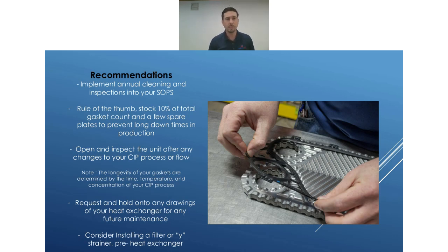A rule of thumb we go by is it's a great idea to have 10% of your gaskets in stock at your facility just in case. If something happens - pressure and you blow out a gasket, or you open the heat exchanger and tear a gasket - you have some readily available, and you're not waiting for us to get you gaskets or dealing with downtime. So it's important that you have those on hand, and a few extra plates just in case.